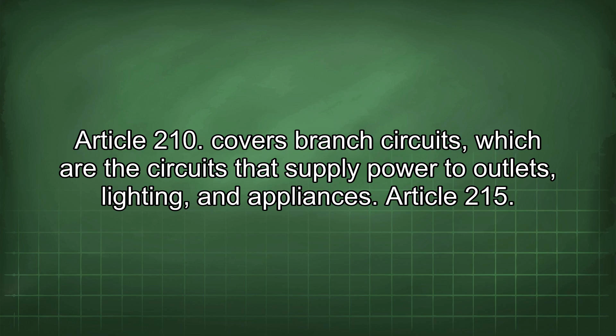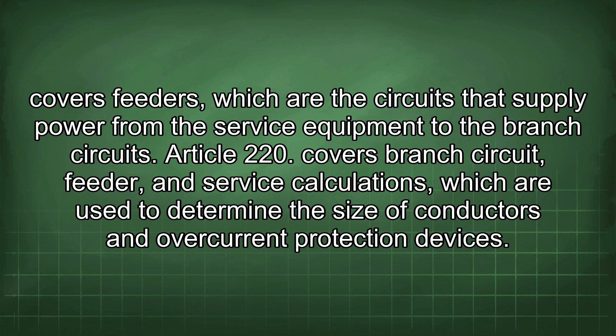Article 220 covers branch circuit, feeder, and service calculations, which are used to determine the size of conductors and overcurrent protection devices. Article 230 covers services, which are the conductors and equipment that bring power from the utility to the building.